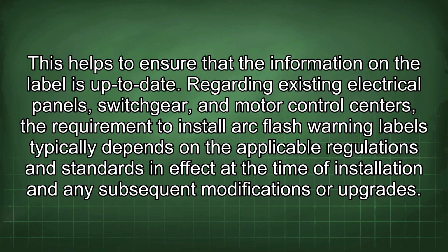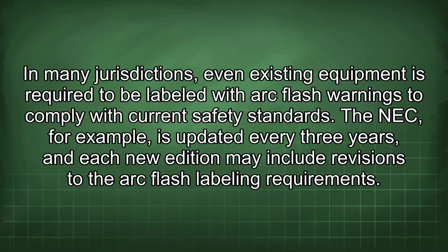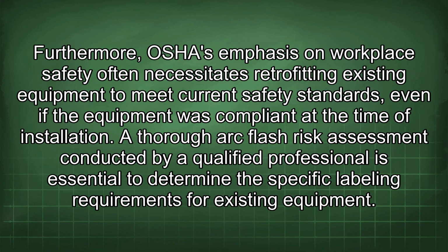Regarding existing electrical panels, switchgear, and motor control centers, the requirement to install arc flash warning labels typically depends on the applicable regulations and standards in effect at the time of installation and any subsequent modifications or upgrades. In many jurisdictions, even existing equipment is required to be labeled with arc flash warnings to comply with current safety standards. The NEC, for example, is updated every 3 years, and each new edition may include revisions to the arc flash labeling requirements. Furthermore, OSHA's emphasis on workplace safety often necessitates retrofitting existing equipment to meet current safety standards, even if the equipment was compliant at the time of installation.